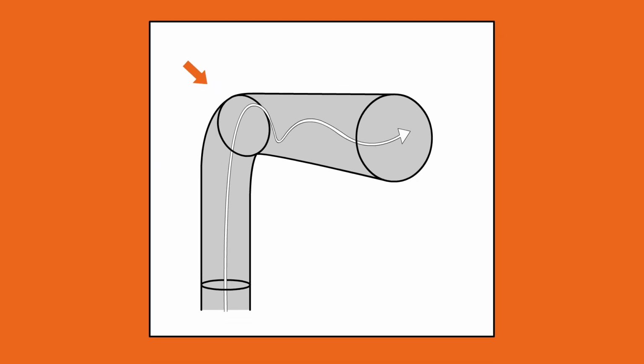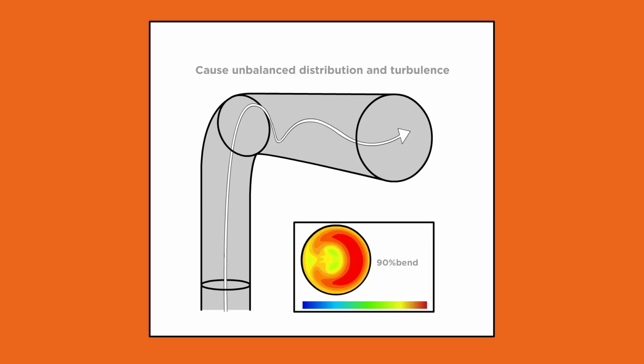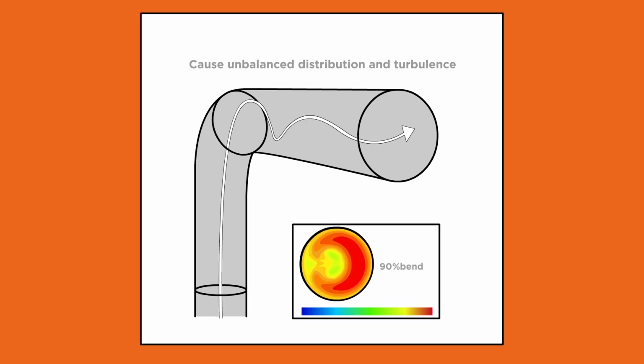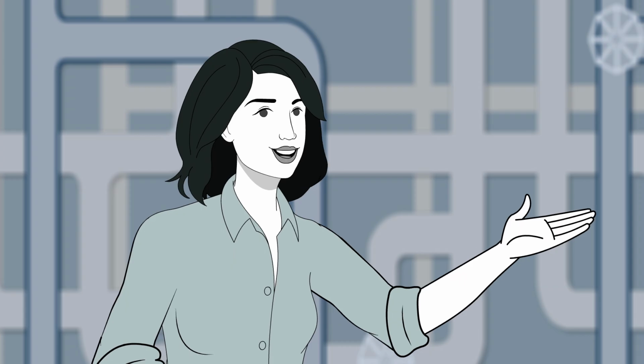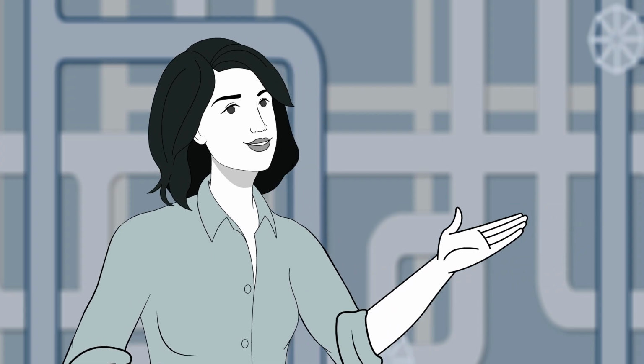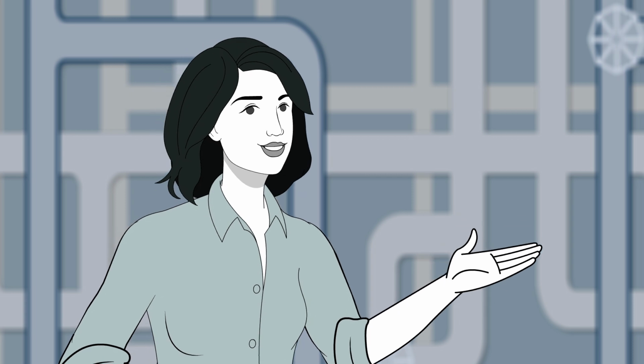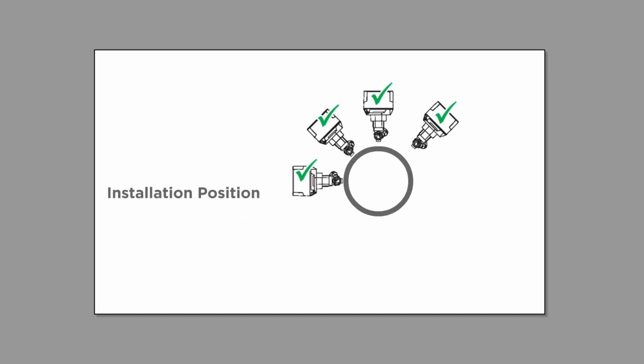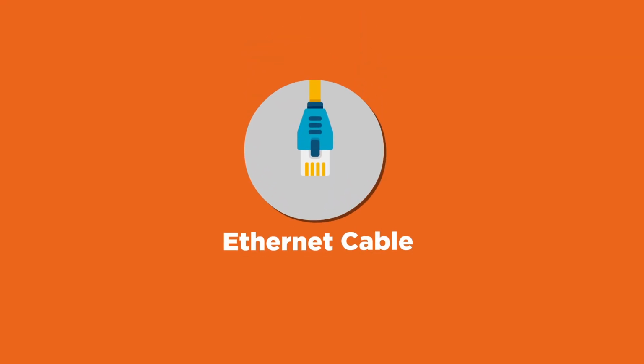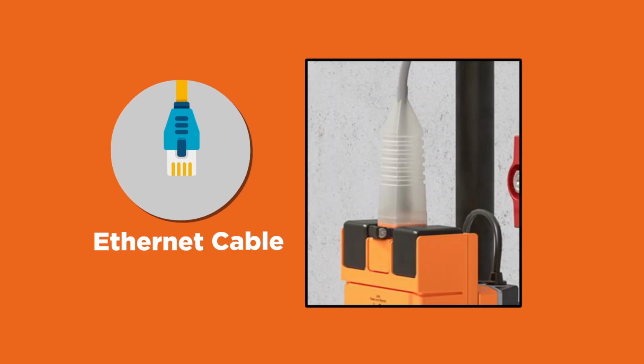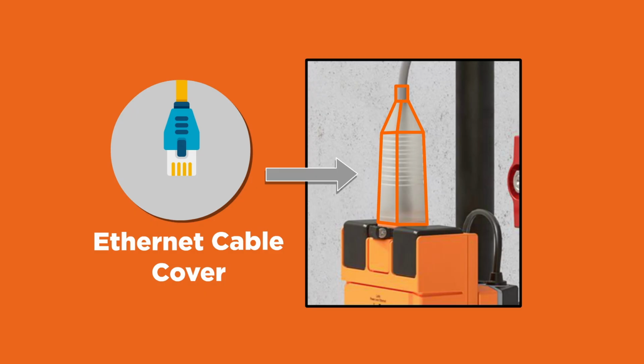When the system's fluid moves through pipe fittings, such as elbows or joints, it tends to get turbulent with unbalanced flow distribution. These disruptions will cause inaccurate flow measurements, so the energy calculations will be incorrect. Users should refer to the thermal energy meter's installation instructions to make sure the meter and external temperature sensor are installed correctly. Thermal energy meters can be installed in a vertical or horizontal position, but should not be installed hanging upside down. If users are planning to use an Ethernet cable to power their meter, they should ensure that they have the protective cover installed to protect against water and dust.